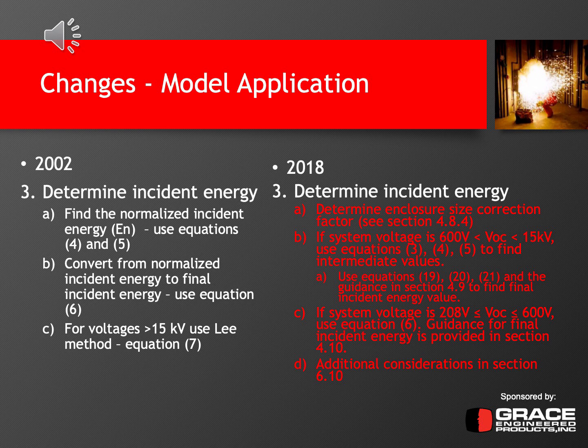And similar to the arcing current, the next step is, if your system voltage is between 600 volts and 15 kV, it says use equations 3, 4, and 5 to find the intermediate values, and then you follow that up by using equations 19, 20, 21, and the guidance in section 4.9 to find the final incident energy value. But if your system voltage, the open circuit voltage, is between 208 and 600 volts, it says use equation 6. So equation 6 is a little simpler, and then guidance for the final incident energy is provided in section 4.10.